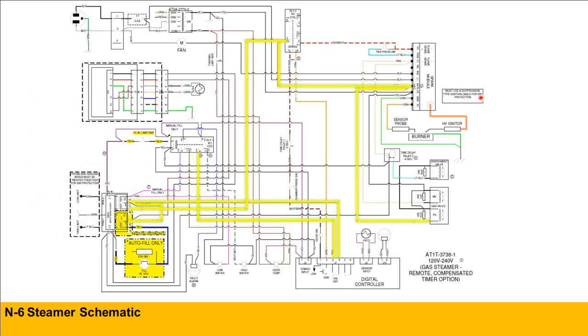Thank you, Dan. All right, so as Dan mentioned, we have a manometer hooked on, and once again, we're looking at a steamer that's not heating. So with the left panel off, before we do anything, what we're going to do is have you turn it on. Now, with the manometer attached to the dual gas valve, the dual solenoid valve, once you hit on, if you see a red light on the module and if you see static pressure, we are moving on, meaning that the AC circuit is running to spec.